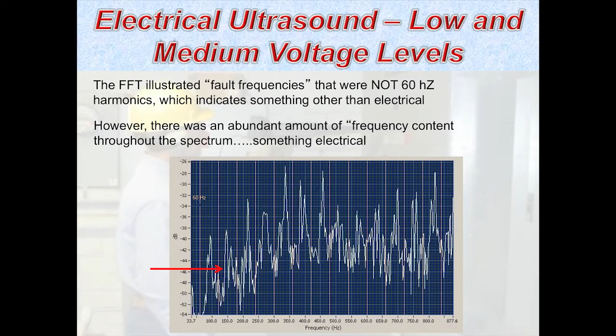On the FFT, the fault frequencies were not on the 60 hertz cursor. Everything we've learned about electrical fault, tracking, and corona - what are we looking for as far as these harmonic frequencies? The base operating frequency. So if I'm on a 60 hertz system, I'm looking for multiples of 60 for it to be some type of electrical anomaly. Looking at this, there's really nothing hitting on 60, agreed? So there's a shift in where this is peaking, and that's got to be caused by something.